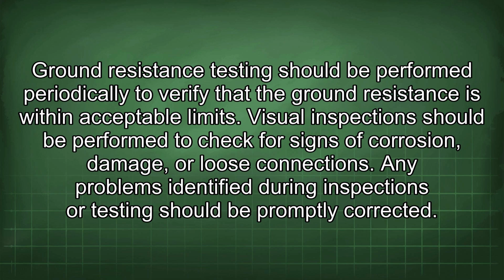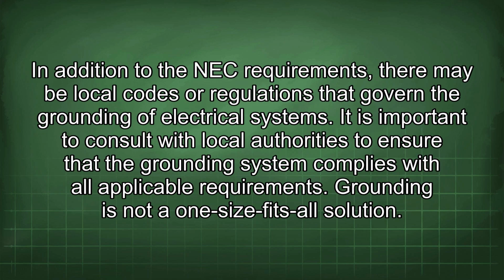Visual inspections should be performed to check for signs of corrosion, damage, or loose connections. Any problems identified during inspections or testing should be promptly corrected. In addition to the NEC requirements, there may be local codes or regulations that govern the grounding of electrical systems. It is important to consult with local authorities to ensure that the grounding system complies with all applicable requirements.